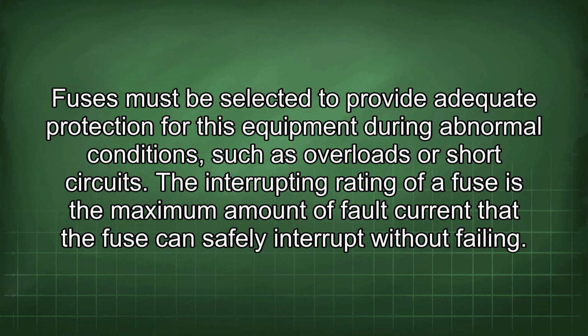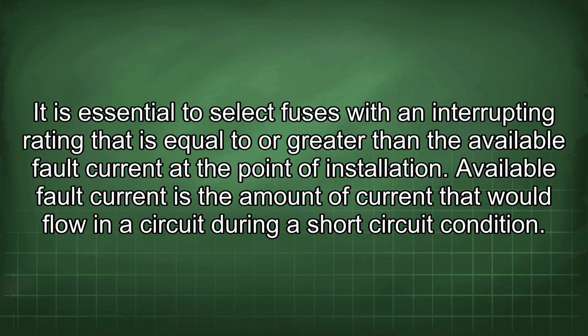The interrupting rating of a fuse is the maximum amount of fault current that the fuse can safely interrupt without failing. It is essential to select fuses with an interrupting rating that is equal to or greater than the available fault current at the point of installation. Available fault current is the amount of current that would flow in a circuit during a short circuit condition.